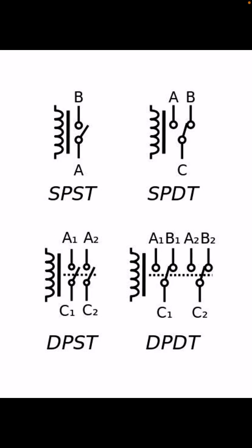Basically, though, what it comes down to in the field and how we use this is, am I getting the proper inputs? And if I am, is it giving the proper outputs? So am I getting my 24 volts from my control voltage from the board? And if I am, then I should be getting the proper outputs. If I'm not getting the proper outputs, then the relay's bad.